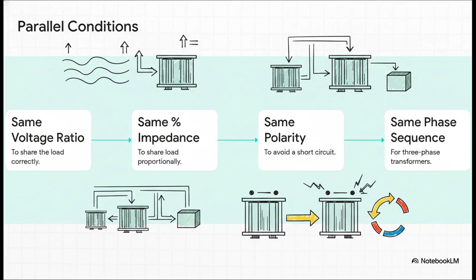This brings us to a classic engineering exam question, a Viva question, that every student has to know. What are the absolute non-negotiable conditions that you must satisfy before you can connect two transformers in parallel? There are 4 critical rules. They've got to have the same voltage ratio, so they share the load correctly. They should have the same percentage impedance, which is basically their internal resistance, so they share the load in proportion to their size. For 3-phase transformers, they need the same phase sequence, making sure their power cycles are in sync. But the most critical one of all is having the same polarity.